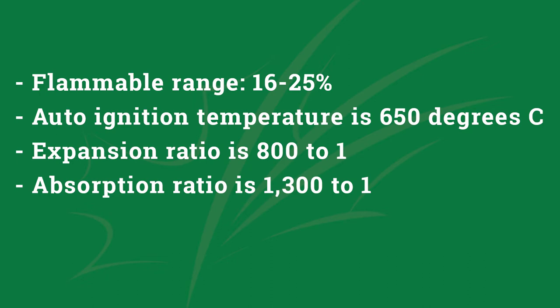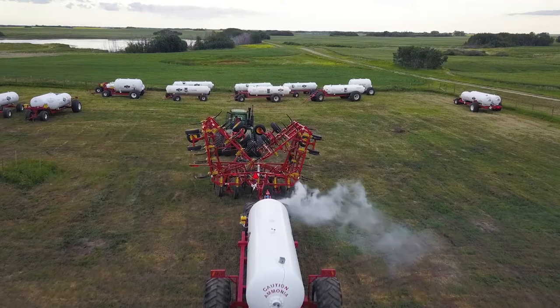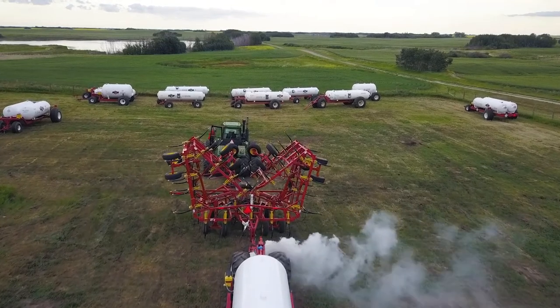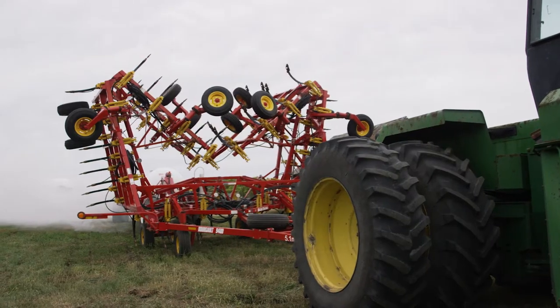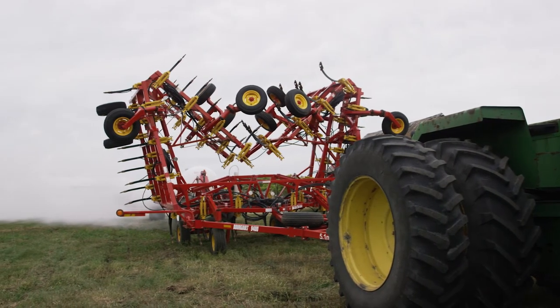The expansion ratio is 800 to 1, meaning that one liter of liquid anhydrous ammonia will form 800 liters of vapor. The absorption ratio is 1,300 to 1, meaning that 1,300 liters of ammonia vapor will dissolve in one liter of water. The vapor density is 0.71 grams per liter at 25 degrees Celsius, meaning that it is slightly lighter than air. Thus, in normal conditions, a vapor cloud of ammonia will move with the wind and dissipate quickly. However, with high humidity, the vapor will take on moisture and could settle and linger in low-lying areas.